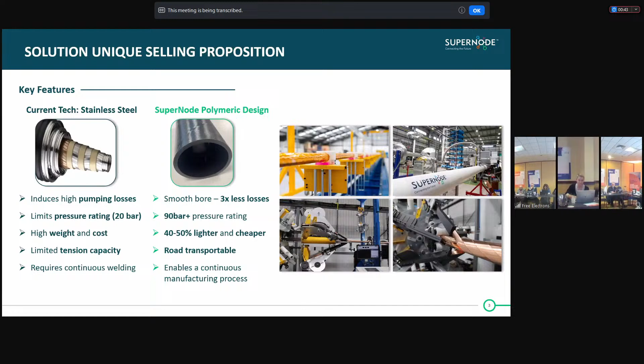Those we call field joints. The cables will be constructed in sections, and we're planning for sections up to 5 kilometers in length, with a joint system between them. It depends on whether it's AC or DC and the voltage levels. What you're seeing on screen is the concept for a DC bipole system, and the joints are effectively plugs. That means you can construct the cables in single pieces, transport them to site, and there's no splicing or joining work done on site—it's effectively a plug system.